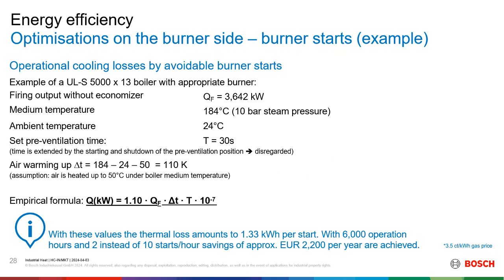During the pre-purge process, the blower fan will come on, force air into the combustion chamber and out of the chimney, to ensure there are no residual gases or risk of backfiring. Then the burner will come on. So by reducing the number of start stops, you reduce the amount of heat picked up by the air flowing through the combustion chamber, which can be saved. Just taking for example a 5-ton 10-bar boiler by Bosch.